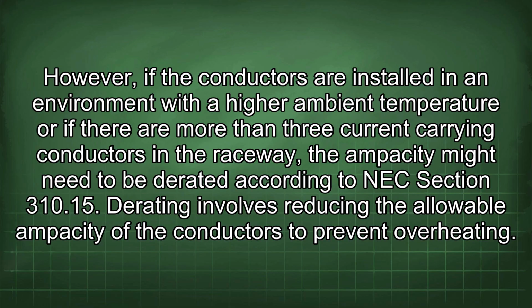However, if the conductors are installed in an environment with a higher ambient temperature, or if there are more than 3 current-carrying conductors in the raceway, the ampacity might need to be derated according to NEC Section 310.15. Derating involves reducing the allowable ampacity of the conductors to prevent overheating.